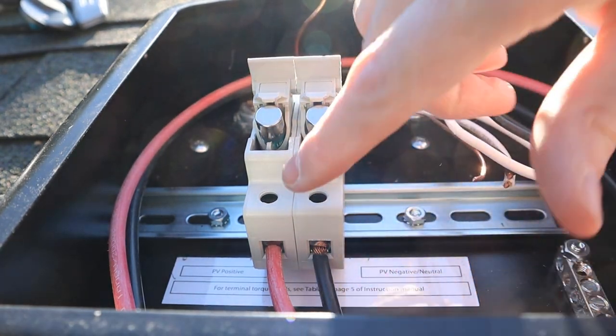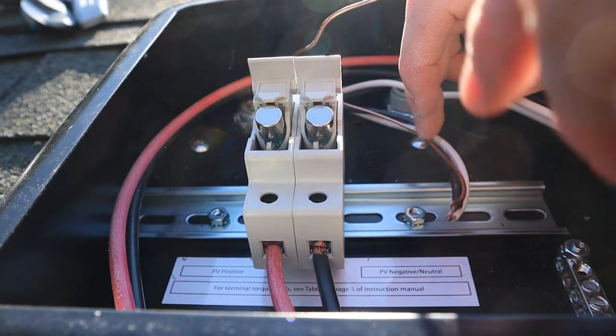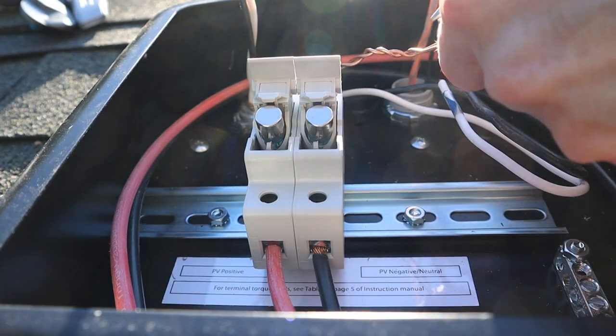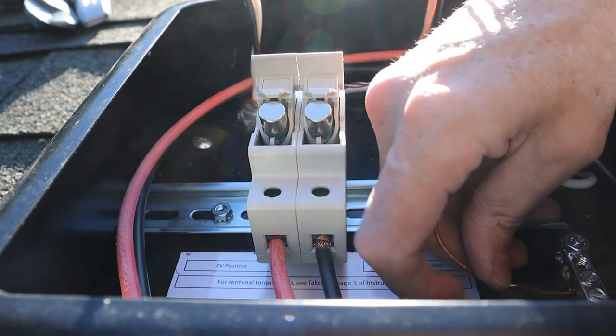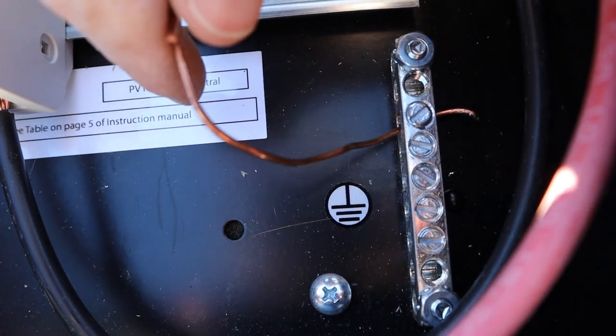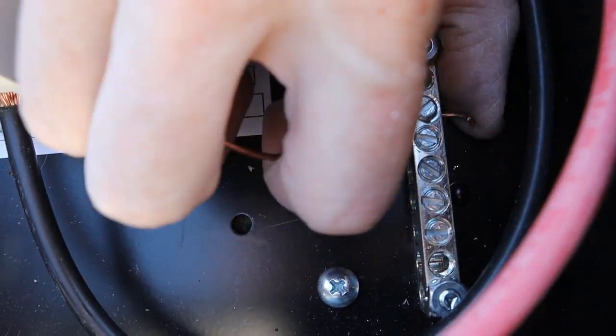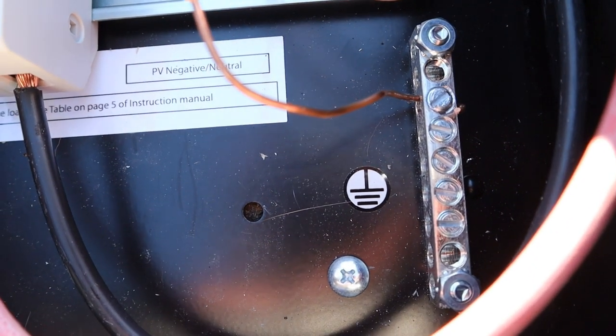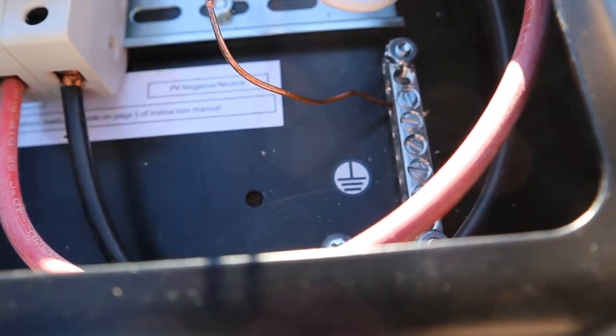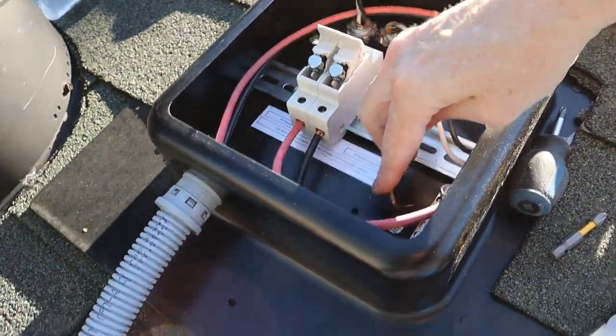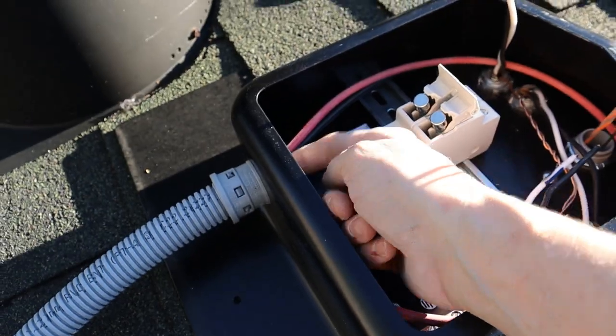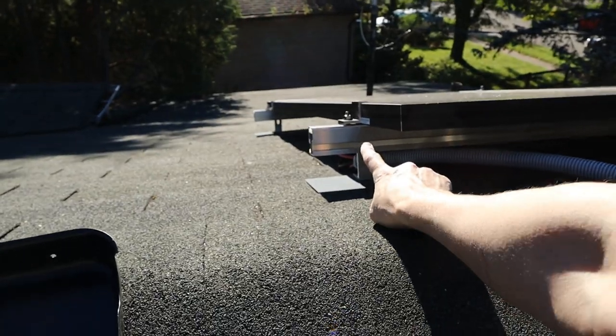These are not connected to anything. I'm just getting them out of the way for now, so they don't risk shorting out against this. The grounding wires, though, I'm going to absolutely connect. So this is the grounding wire in one of the BXs going to the grounding rail. Okay, and next time I'm up here, what I will do is I'll strip out some of this grounding wire from some spare wire I have, and I'm going to run it down the conduit that these wires are in that goes to the solar panel, and I will tie it to the frame to ground all the framing.